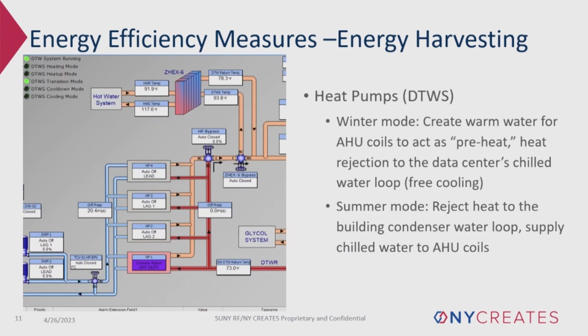Our second energy harvesting measure that I would like to discuss today is the water-to-water source heat pumps. In the winter, these operate in heating for the airside coils using the chilled water from the data center. In the summer, these operate in cooling to pre-cool the makeup air before we send it into the spaces.